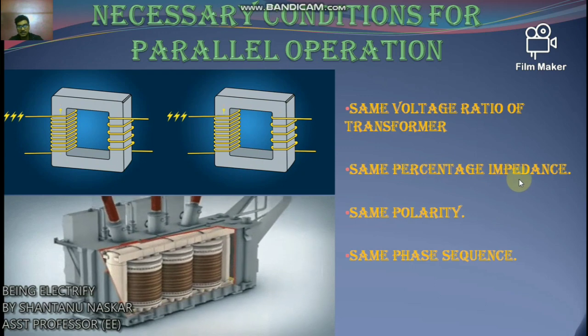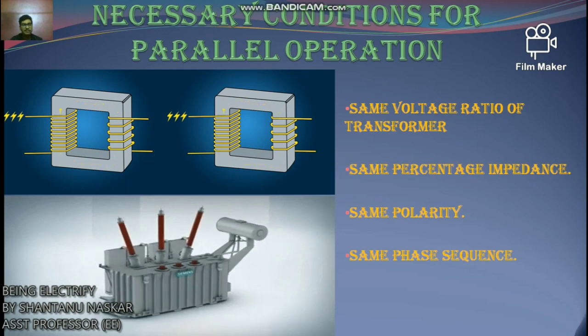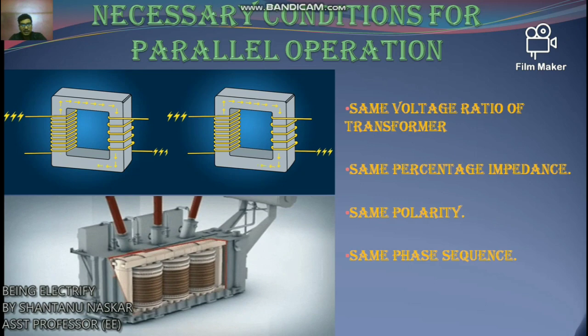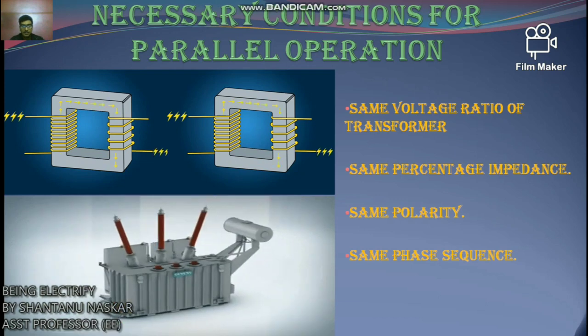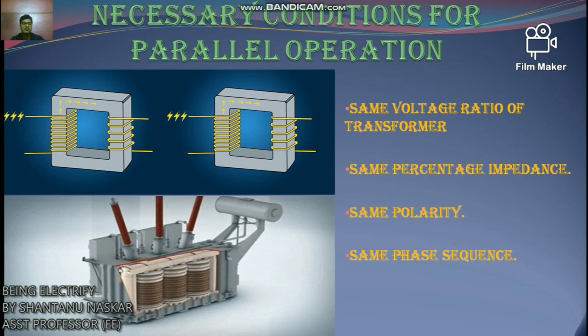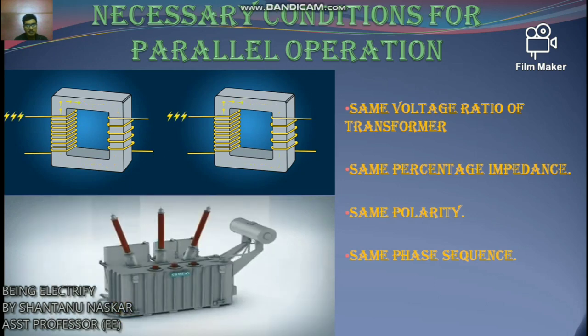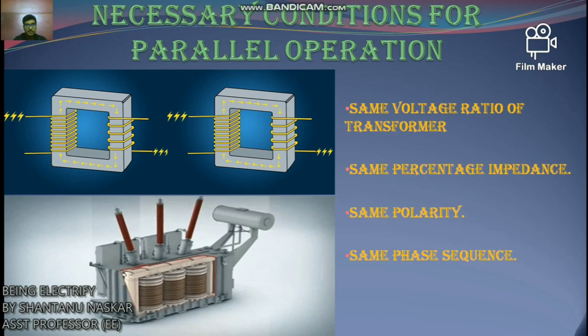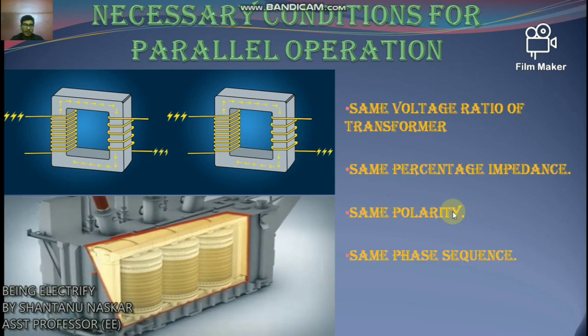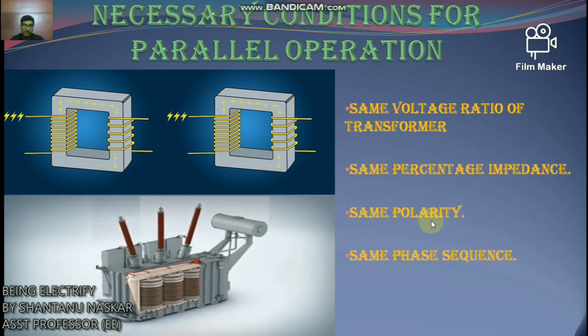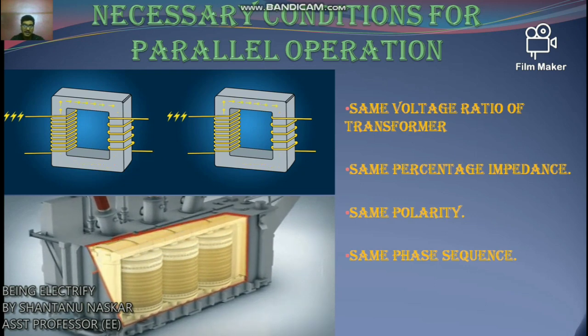Number two: same percentage impedance. The current shared by two transformers running in parallel should be proportional to their MVA ratings. Current carried by each transformer is inversely proportional to its internal impedance. Therefore, the impedance of transformers running in parallel should be inversely proportional to their ratings, meaning percentage impedance or per-unit impedance values should be identical for all parallel transformers. Number three: same polarity. The polarity of all parallel transformers should be the same; otherwise, a huge circulating current will flow.